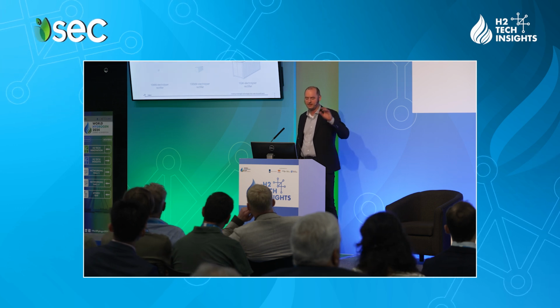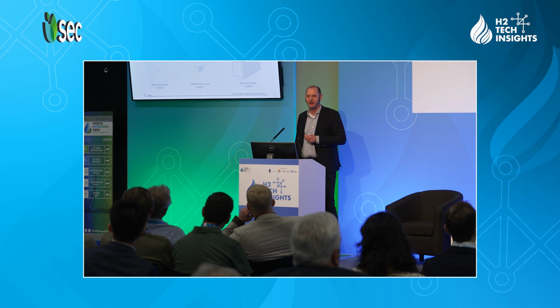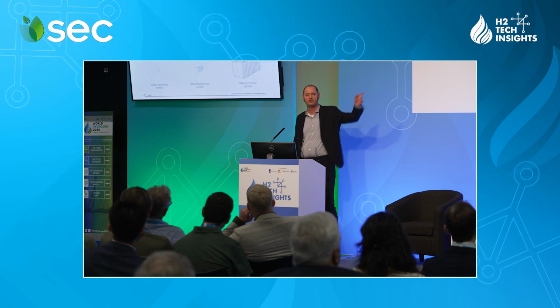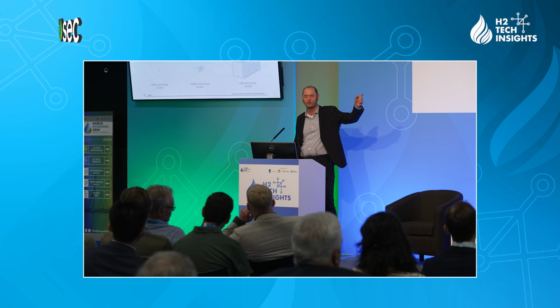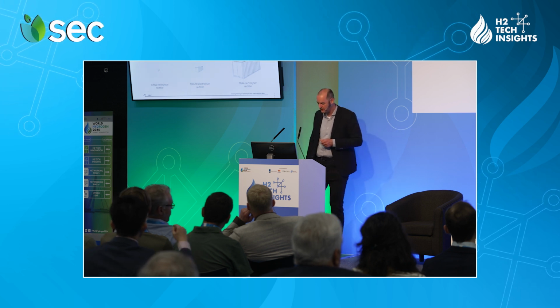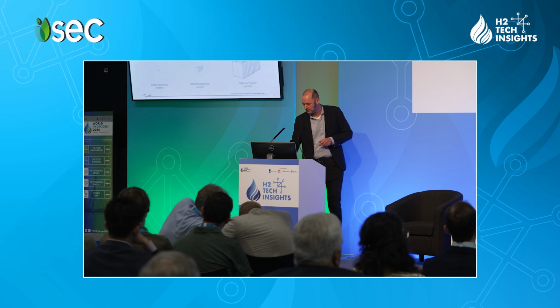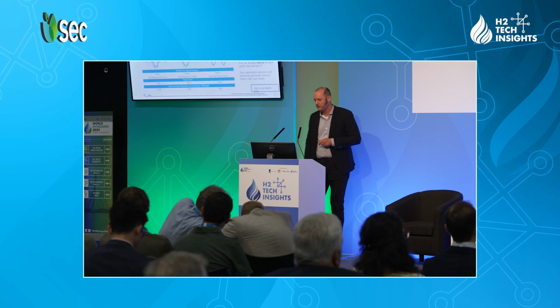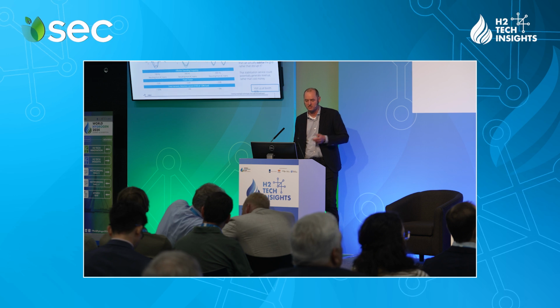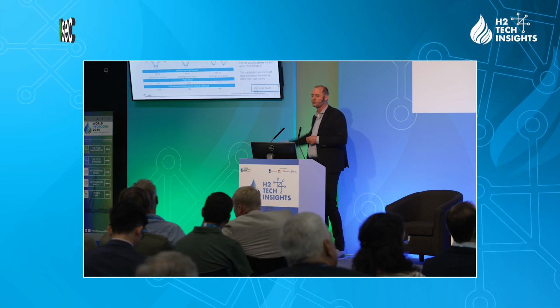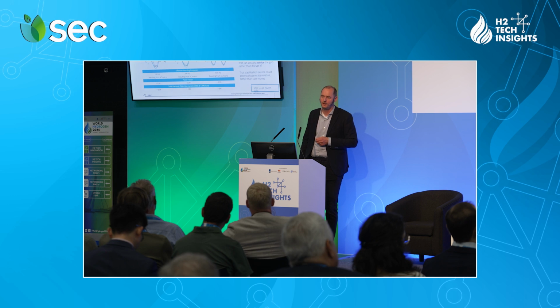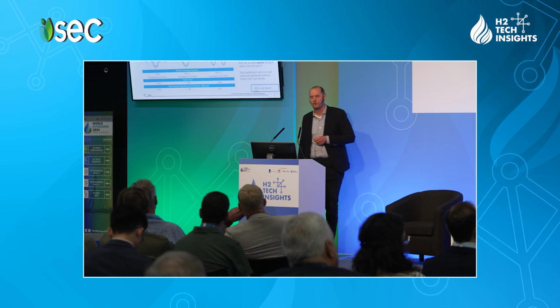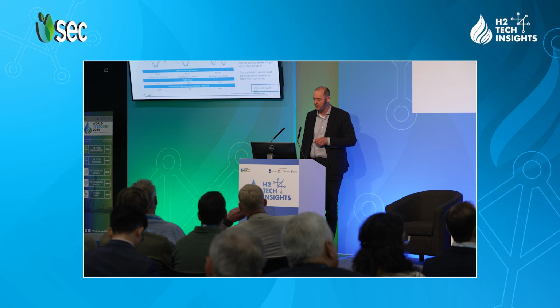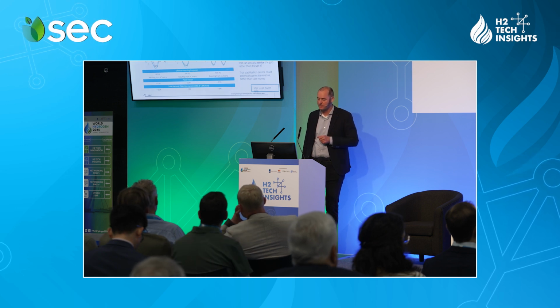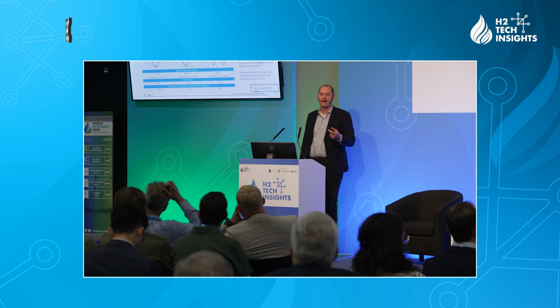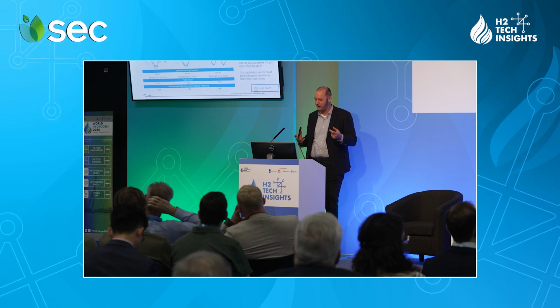So if you think that by having a 10 megawatt project, and that works fine, that you can immediately scale that up to a gigawatt without taking total harmonic distortion into account, you're sadly mistaken, unfortunately. So it's something you really have to take care about. So if you look at old school technology, so thyristors, in order to get to a sort of sinusoidal waveform, you really need a lot of hardware next to the thyristor converter. And this hardware also has very long lead times. So to even make it work at scale, you need that hardware.